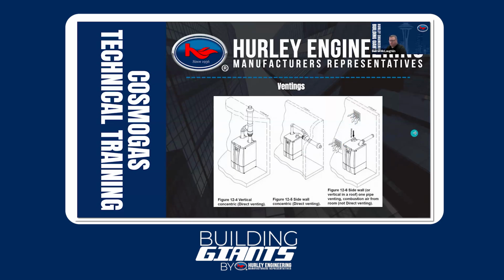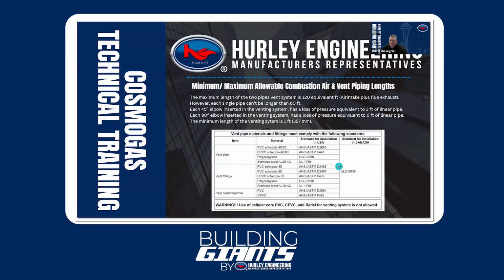So, as far as vent materials go, PVC, CPVC, polypro, stainless steel. If you're not sure if what you have matches, here are the applicable codes in the US that dictate what is good for this application. So stainless steel, if you need AL294C, there are different versions of AL294C. As long as they meet UL 1738, CosmoGas is happy that they'll be fine for their equipment. Same thing with pipe and fittings, UL 1738, or the other ANSI ASTM codes. They even give one for the pipe, cement, and primer you should use that it meets certain ANSI and ASTM codes as well.